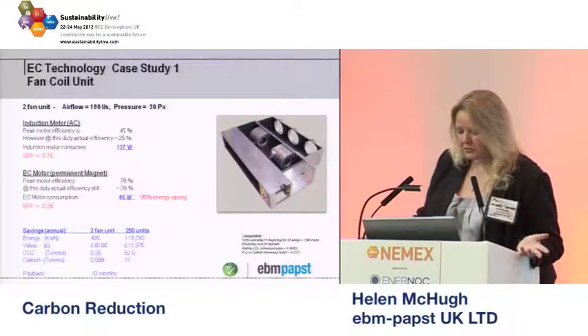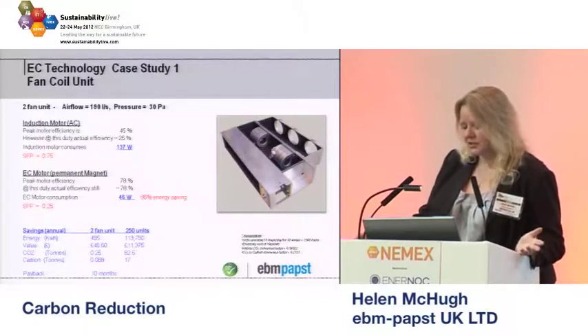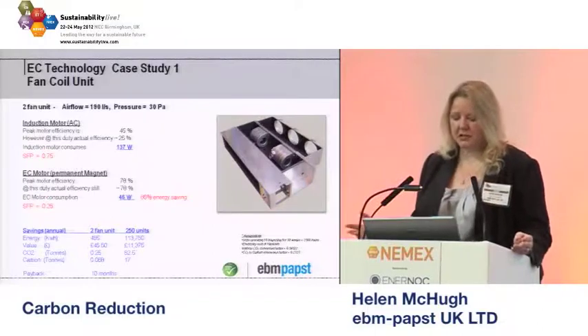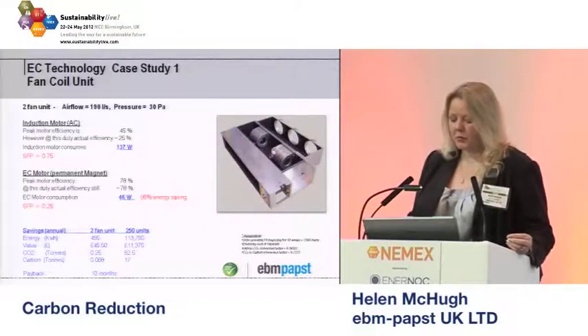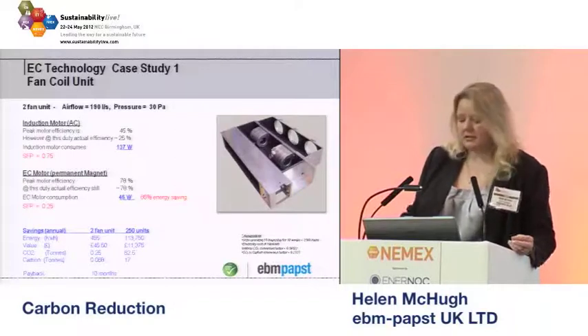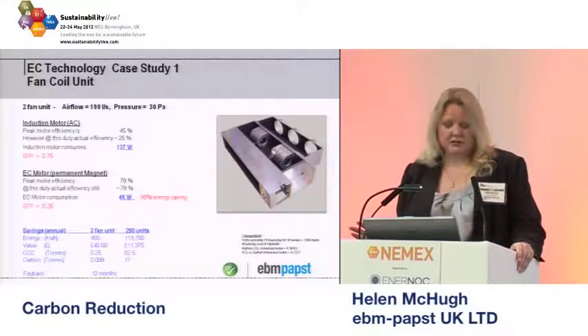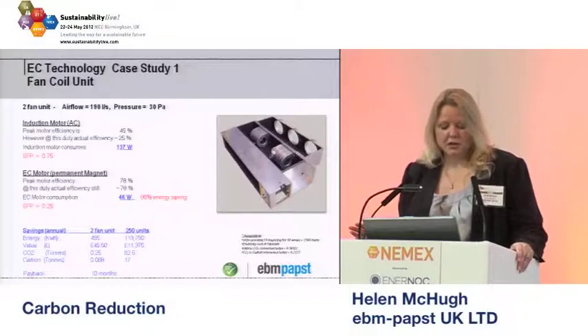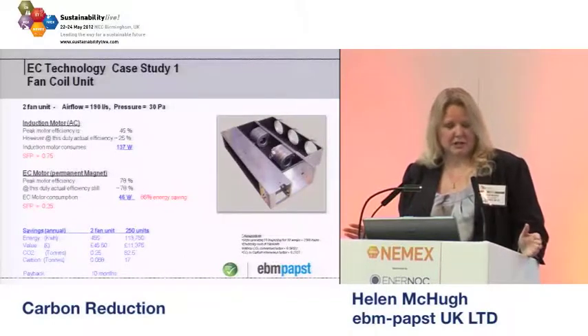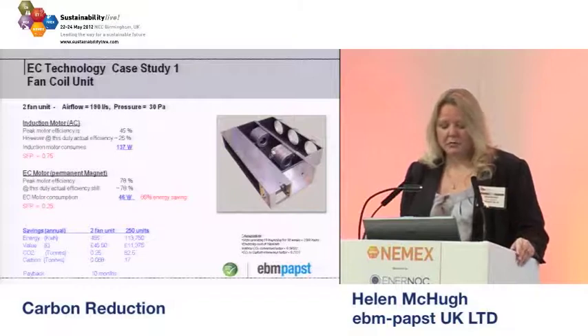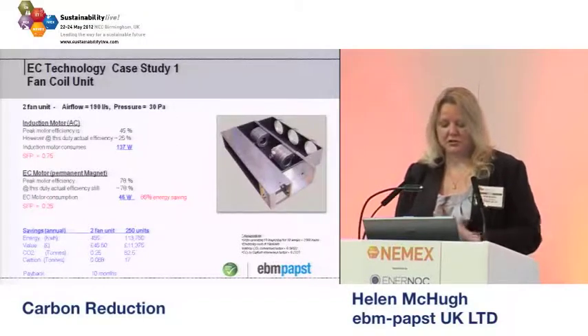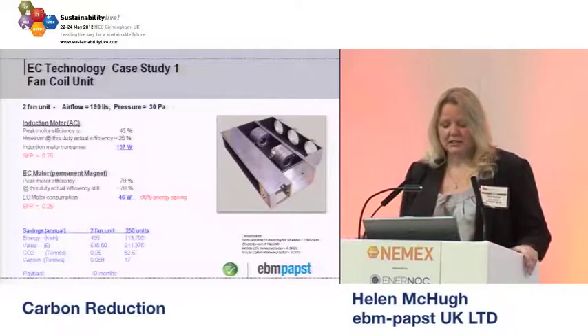So getting on to a particular case study, this is a fan coil unit which many of you will have in your buildings, and this particular one for a large telecoms company. And so they replaced their double fan unit, so you see there 2 AC fans, swapped out for identical dimension EC fans, and on paper the AC motor is looking at about 45% efficient, which is particularly low anyway, but in reality, because it's squashed into a space that's not ideal for it, it's actually operating at around 25% efficient.